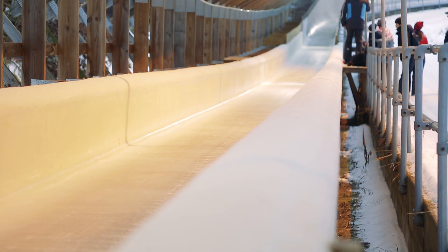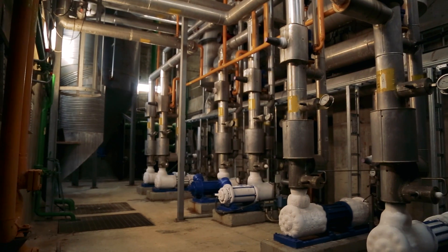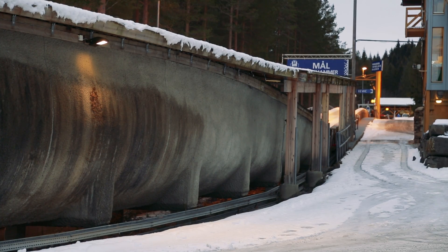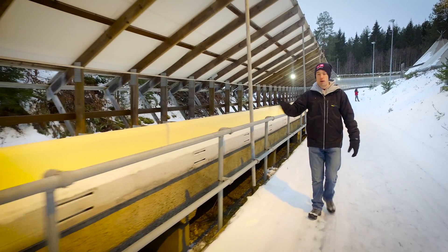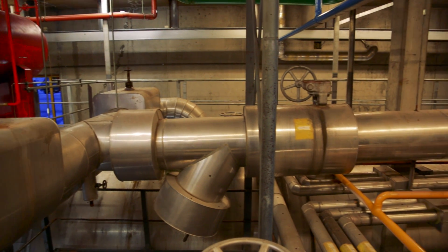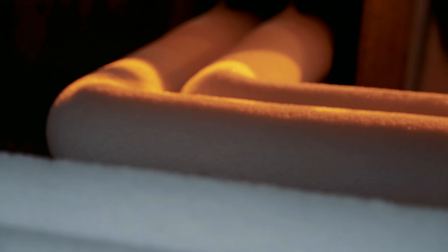We can keep it frozen during the summer in a normal Norwegian summer. It's built with concrete, and inside the concrete there are lots of layers with pipes. Inside the pipes, ammonia is running. When a liquid evaporates, it pulls in heat from the surrounding area. So there are 90 tons of ammonia circulating in pipes underneath the track, being repeatedly compressed and then evaporated to move heat away.